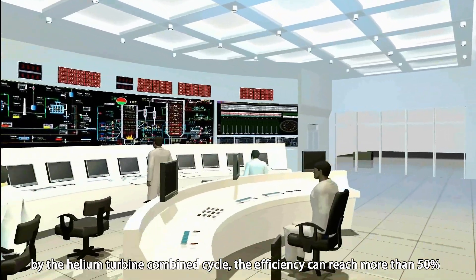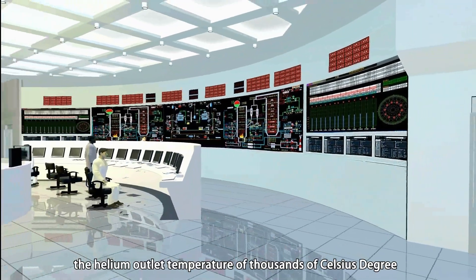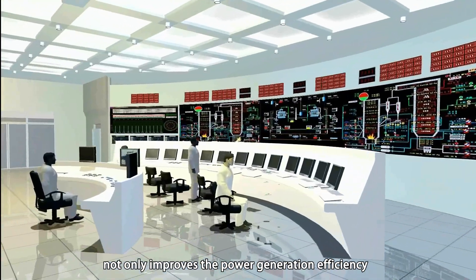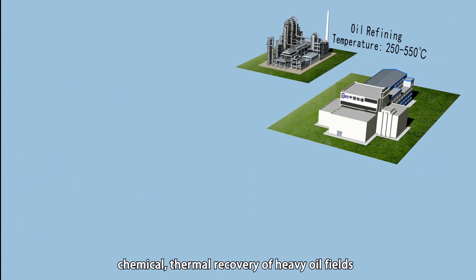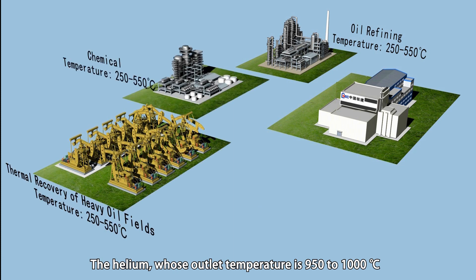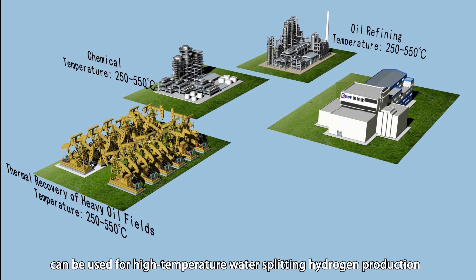The supercritical steam power generation efficiency can reach 45%. By the helium turbine combined cycle, the efficiency can reach more than 50%. As an advanced type of reactor, the helium outlet temperature of thousands of degrees Celsius not only improves power generation efficiency, but also supports a variety of industrial applications. For example, it can supply high-parameter steam for oil refining, chemical processing, and thermal recovery of heavy oil fields. Helium with an outlet temperature of 950 to 1000 degrees Celsius can be used for high-temperature water-splitting hydrogen production.